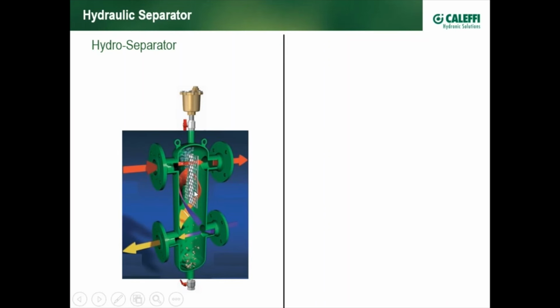We do have a baffle plate. The baffle plate serves the purpose of making flow that could otherwise be turbulent, laminar. Turbulence means pressure drop. We don't want pressure drop. We want minimum pressure changes, or minimize pressure drop. And also, the baffle plate has been perforated with sharp edges, giving it a coalescing feature. So in addition to hydraulic separation, it also gets rid of air.